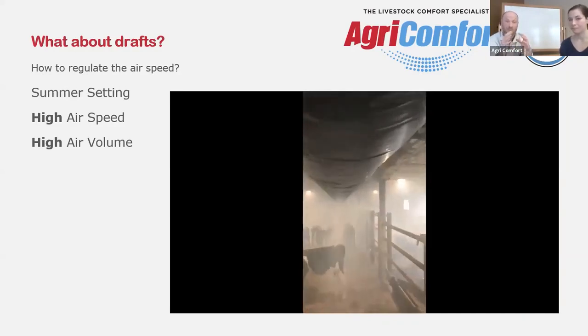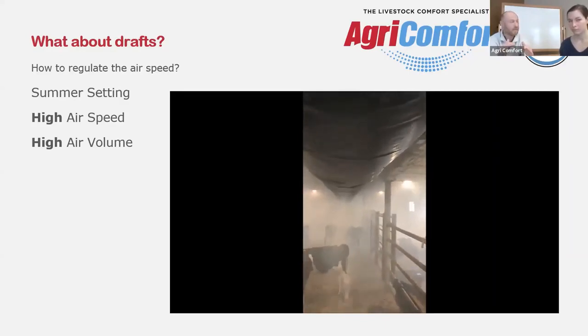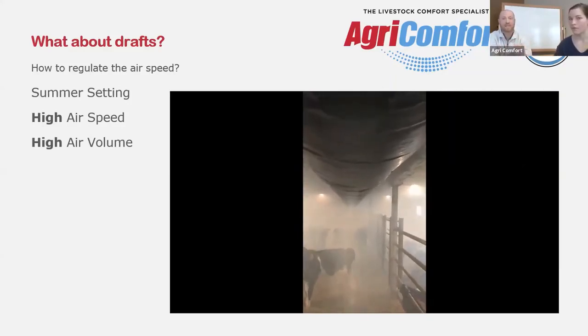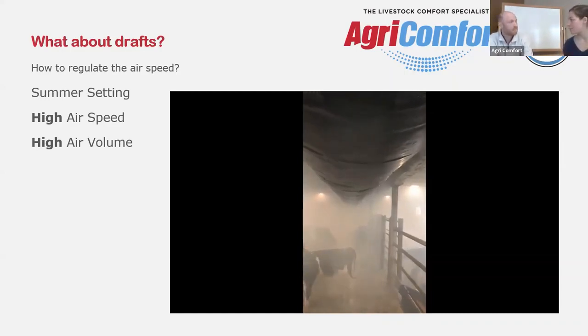And you'll see we blow that air straight down into the calf space, and we're effectively ventilating the air that the calves breathe, and we're providing a cooling effect by blowing the air on those calves. And another nice effect in summer is that flies really don't like high-speed air. Correct. Or drafts in any kind of temperature, and they just try to avoid it. They cannot really fly and maneuver that well in it, so they try to stay in low airspeed areas.